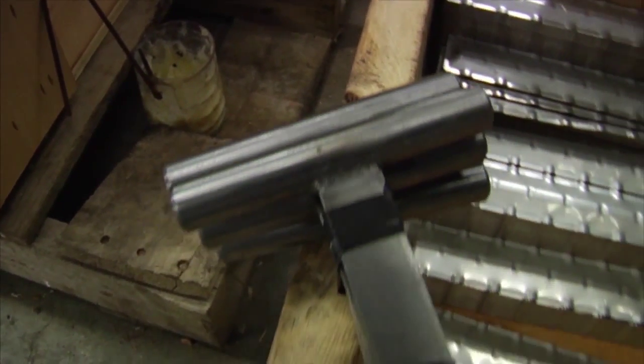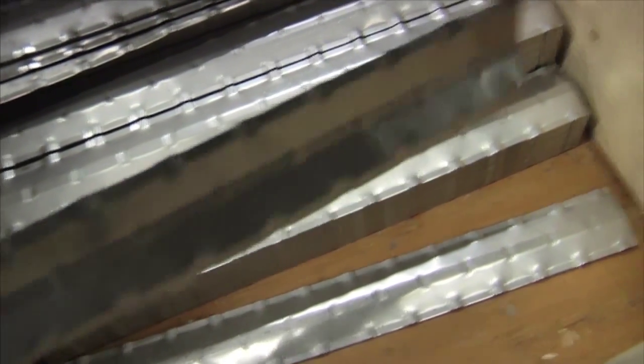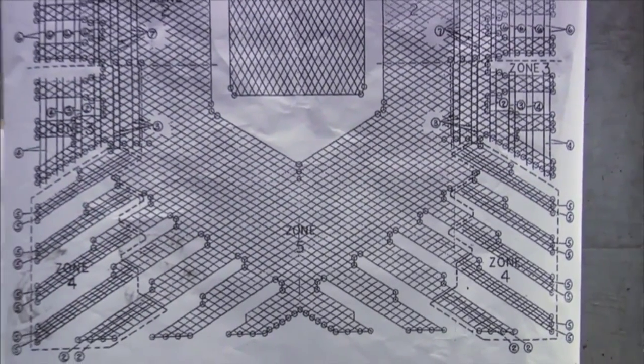So we came up with the cradle lock stake. I worked on this for a lot of years and finally came up with a design that actually locked each tube into position along the device. It's a metal bar made out of 304 stainless steel. It's custom engineered and it has dimples in it. We come up with the spacing of the dimples and the depth of the dimples. It's unique to the condenser design that we're working on, the tube material and the tube spacing. And it virtually locks the tube bundle into a vibration-free unit. The design and the testing of the stake starts way before the retubing does.